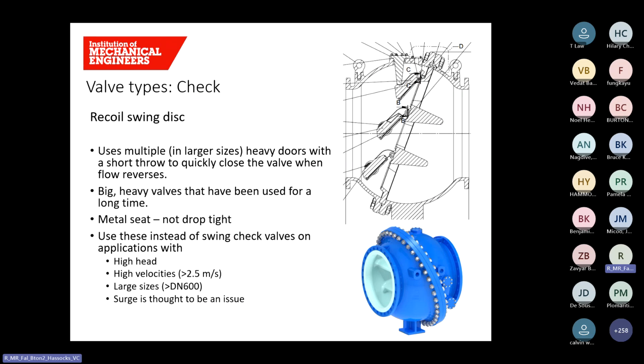Another check valve, which is less common, but we still use a lot of them in the water industry, is the recoil swing disc valve. This valve has a number of openings or doors which open when the flow passes through it, and the purpose is for these to close more quickly than having a single door that opens, and therefore you get less likelihood for reverse flow and surge occurring. They tend to be used on bigger pipework, bigger diameters, and they're big, heavy valves. They have a metal seat, so they're not drop tight. There is a little bit of leakage, and they tend to be used on high head, high velocity applications, particularly where there's a history of surge occurring.